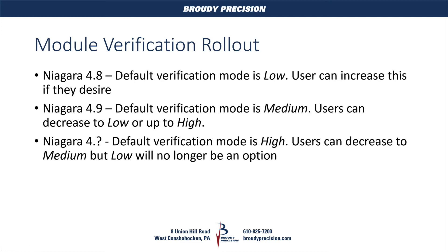So what does the rollout look like for Niagara? In 4.8, the default verification mode was set to low, so you would see an error message in your application director but all your code would still function properly — you were just aware that something was going on. In 4.9, they've changed the verification mode up to medium, meaning code or modules that are not signed at all will not open or run. You can change this by decreasing it to low or moving it up to high, but out of the box it's set to medium.